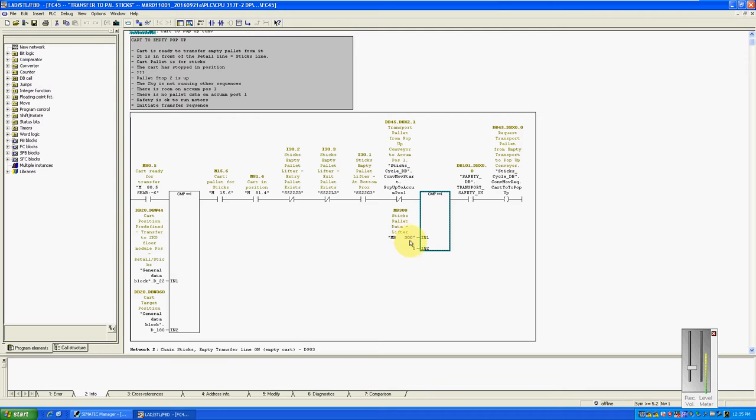So I've got to at least have no states. I can't have any pallet data on the lifter. You can actually add and delete data on the HMI to match what's physically there. So if the PLC thinks there is something there, but the sensor says there's not, it actually won't transfer there, and it'll hang, essentially. And because this is in my transport safety zone only, I only need my pallet transport to be okay. To run from the pop-up to the accumulator, I'm going from the transport zone to the sticks and retail zone, so in that one I'd want to have both safe.